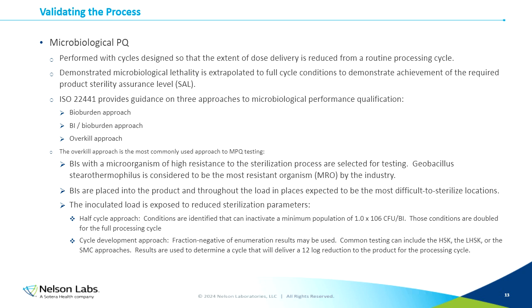And then finally, most people will be familiar with what is termed the overkill approach. The overkill approach is when we use a very resistant organism in high numbers to deliver a sterilization process that is well in excess of what's needed to inactivate product bioburden. And as mentioned on the slide, the overkill approach is the most commonly used approach when we're performing microbiological performance qualification testing.